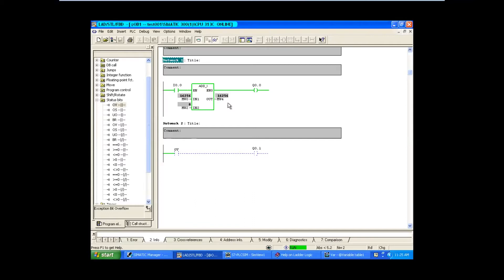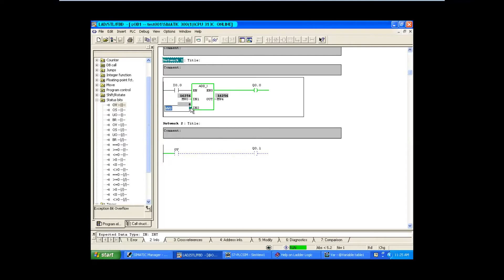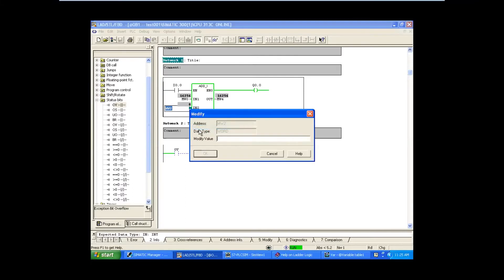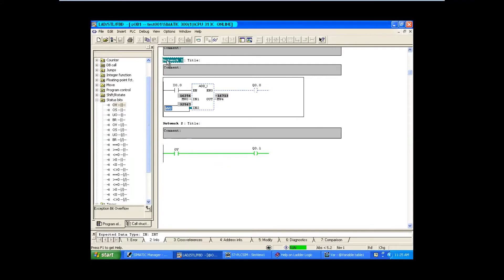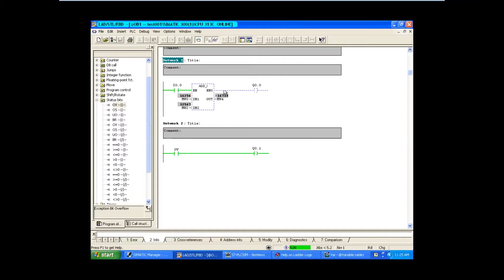Below 32767, the overflow bit is off. Suppose if I change the value - now if both values are added the result will be beyond our limit. You can see MW4 is showing some wrong value; it cannot add because this is beyond the limit of the addition block. At that time your overflow bit will be turned on.